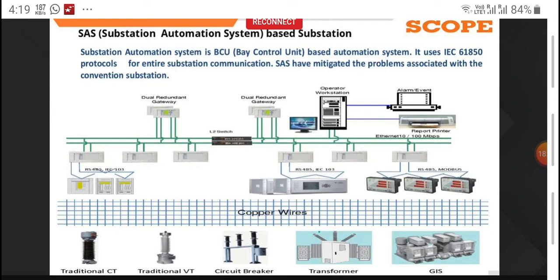For relays, today everybody has moved from static relays to numerical relays, and numerical relays with the IEC 61850 protocol. So most of the relays communicate with the substation automation system through 61850. Earlier, the protocol used to communicate with substation automation was IEC 60870-5-103. So some old relays are still there, still communicating with the substation automation, because this 103 protocol is a serial protocol, not an IP-based networking protocol.